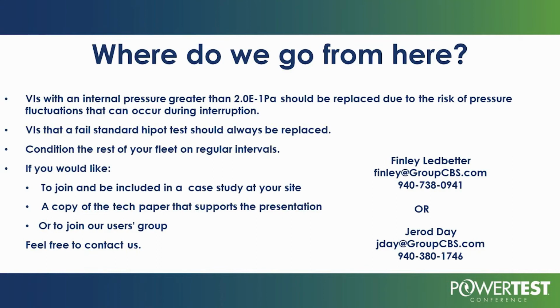It's a very viable process, and I think we're going to find some interrupters with high ion current that we can affect and help, but we have seen some where the effect is very negligible when you get right down close to the knee of the curve where it's about to fail. Where do we go from here? VI interrupters that are near failure need to be replaced. VI interrupters that are beyond wear limits need to be replaced. Interrupters that are in the middle of their life cycle need to be kept there as long as possible. We can take this fleet of interrupters, hundreds and hundreds of millions of dollars' worth, this critical piece of the infrastructure in the United States, and extend its life.